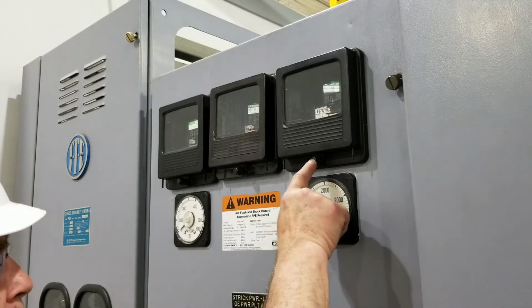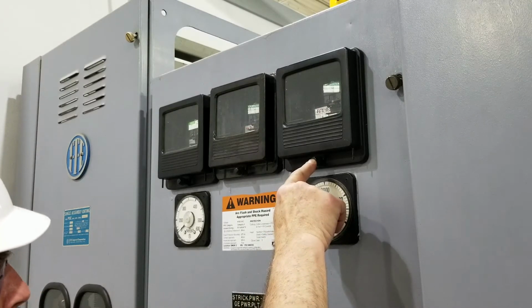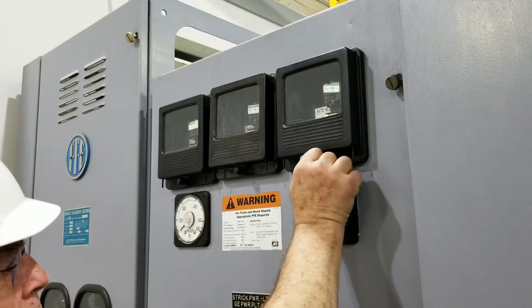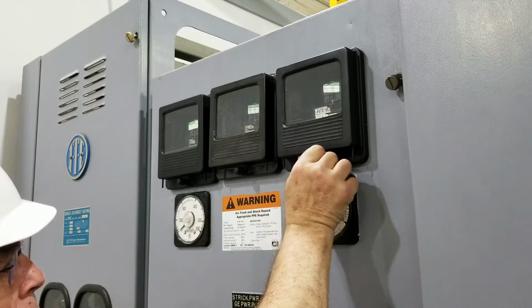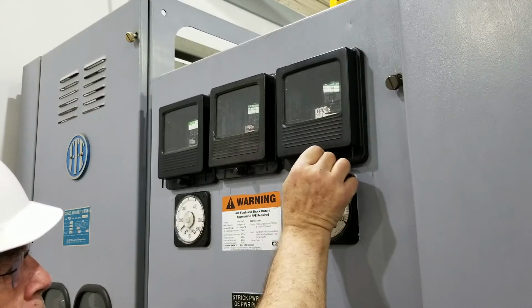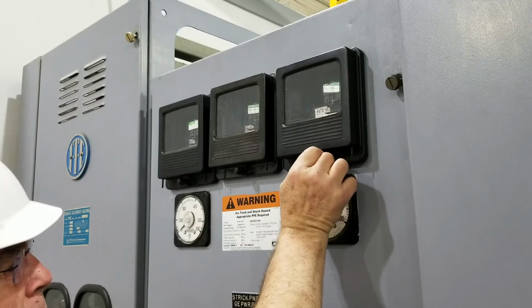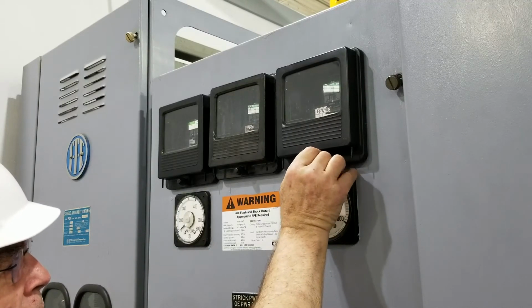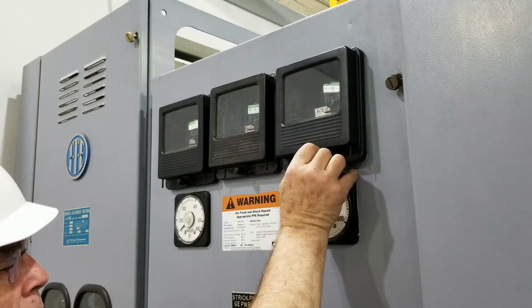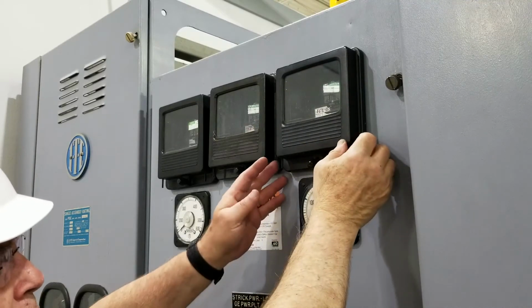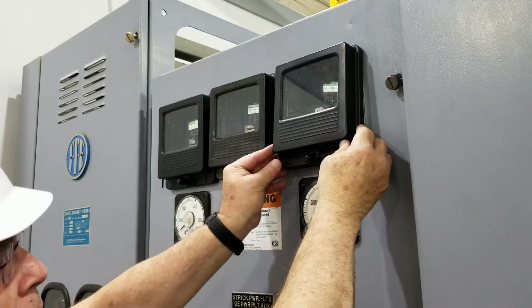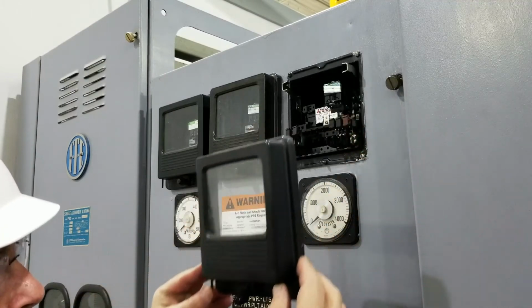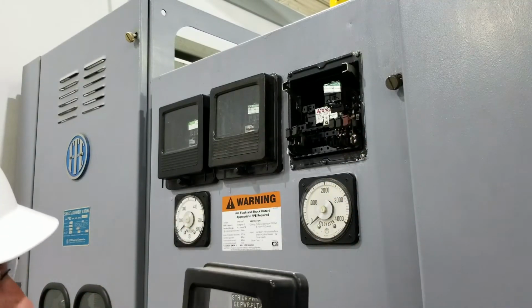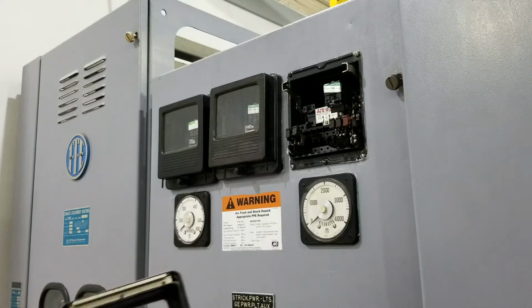Now notice on the Westinghouse relay there's one thumb knob located right here. We'll go ahead and loosen that thumb knob until it's completely loose and the cover is loose. Then we pull slightly out and lift up, and the cover comes right off. Again, we have our designated place where we're going to lay this on the test table.